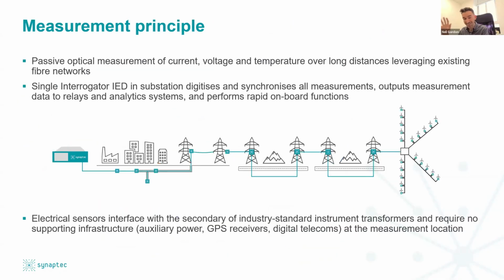So that's an introduction to the technology, and now we're going to look a bit deeper at how it works. It allows measurements of current and voltage and temperature to be deployed over distance, but how does that really work? What we do is leverage the existing single mode fiber that is installed in most modern power networks alongside cables or in the OPGW, the optical ground wire on the overhead line, and we use that to install our sensors at these remote locations. As you can see from this little cartoon, we can reach out over a wide area throughout different parts of the network infrastructure and install these sensors for measurement of voltage or current or temperature in series along that fiber. Any one of these sensors could be any one of those different measurands.